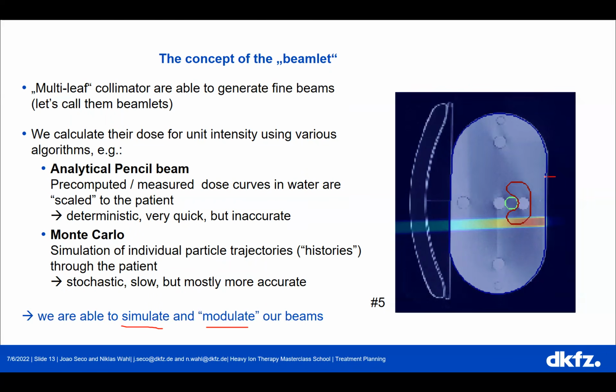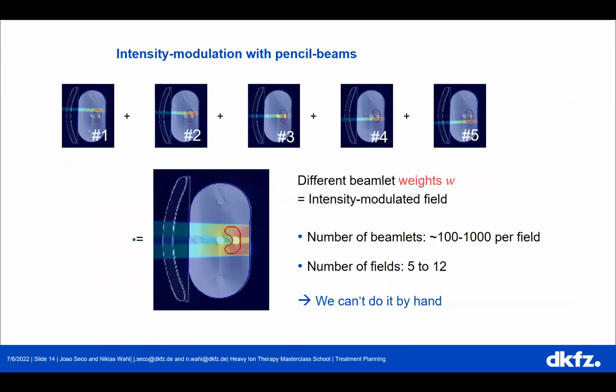So remember, before I had a uniform intensity coming in. With the power of the beamlets, I can change this intensity to have any type of intensity that is needed. So I could change intensities to be like this. So like this, I have a variable intensity, or the previous one, I have a uniform intensity. So adding up these beamlets, I can produce any shape of beam, and I could even control it such that I can put more dose to the edges and less dose to the middle, protecting the organ from radiation, right? Usually you have 100 to 1,000 beamlets, sometimes even more per field. So if you have many fields, you have sometimes in the order of 60, 70,000 variables that you have to optimize for. And this requires computational tools that are capable of doing that.